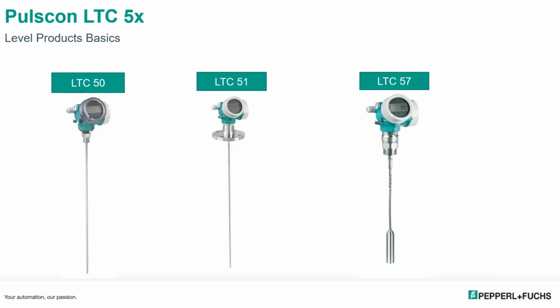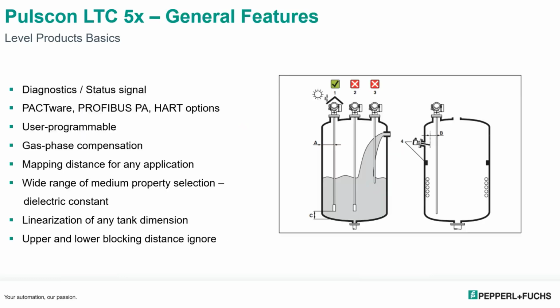Now, Pulscon's LTC5s are the guided wave radar systems, the LTC50, 51, and the 57. The Pulscon LTCs offer some unique features. They have diagnostic status signals, where it can indicate when something's interfering with the signal and so on. It can come with PACTware, Profibus, HART. They're user programmable through the PACTware or through the display. They have gas phase compensation, so you don't have to worry about that. You can compensate that out.